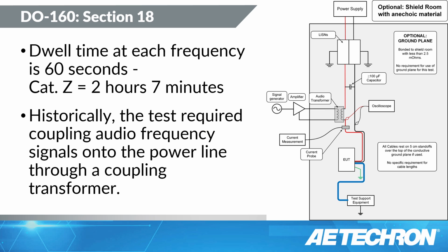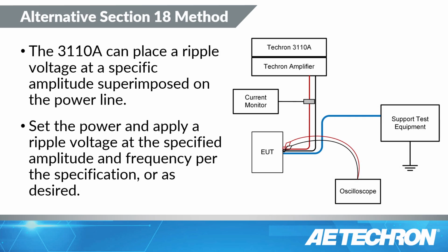However, I was asking about this test to the committee, and I said, well, is there a reason why, especially with a situation if you have an AE Techron that's supplying the power, DC power, and it has the capability of putting a ripple directly onto the power line, can you do that? And the answer was, yeah, there's really no reason not to perform that test that way.